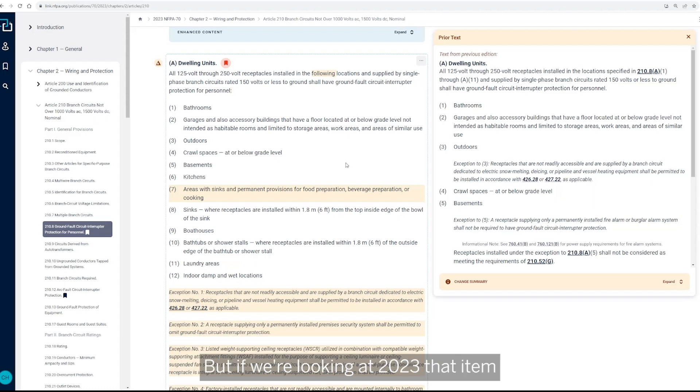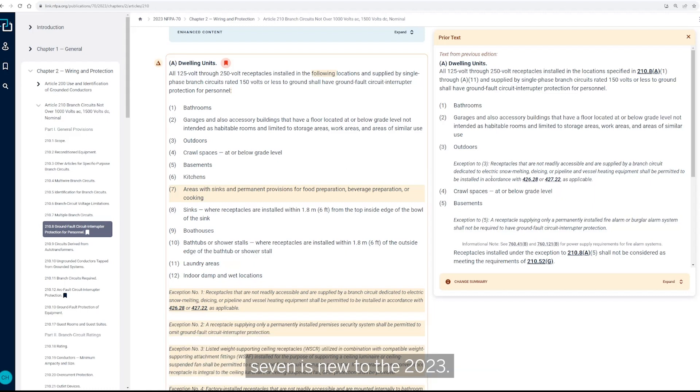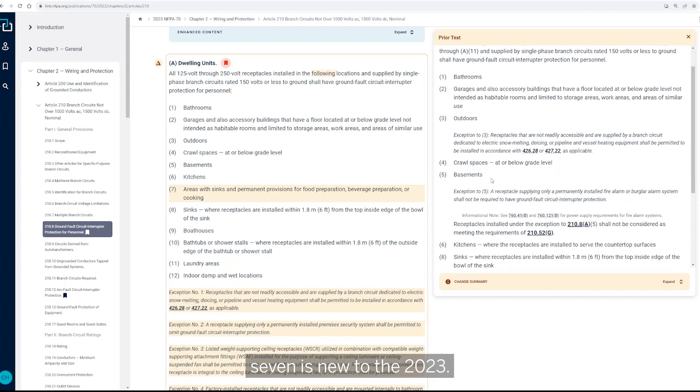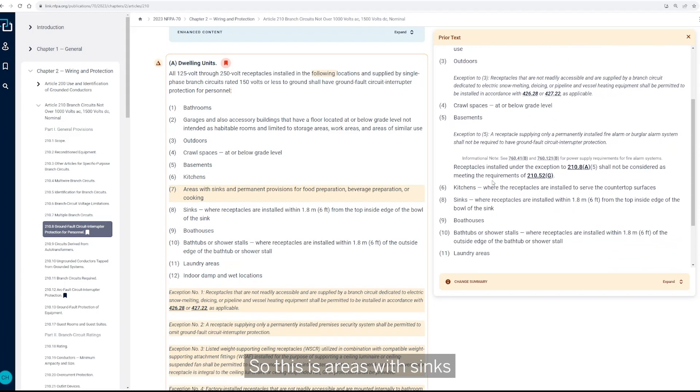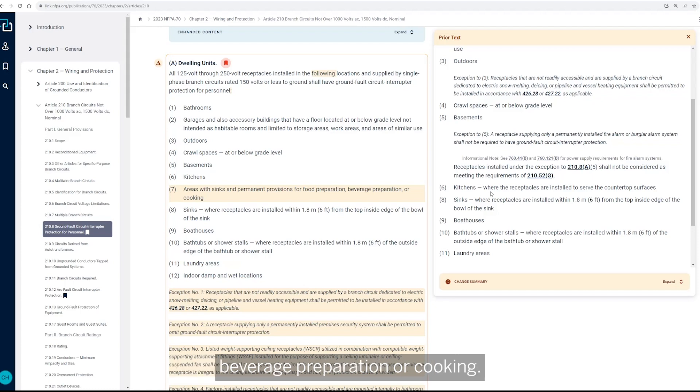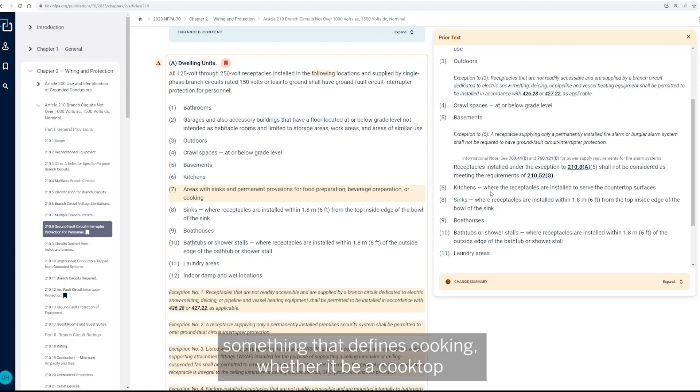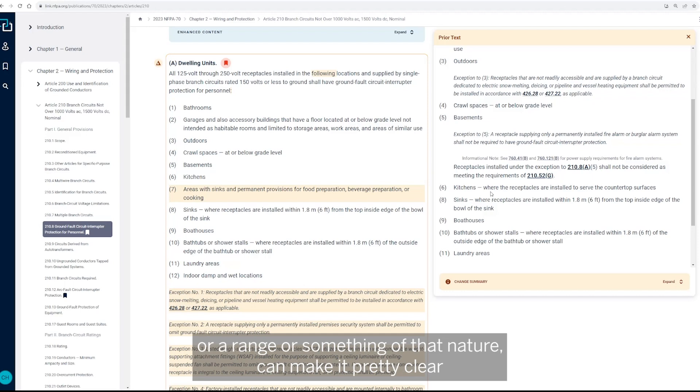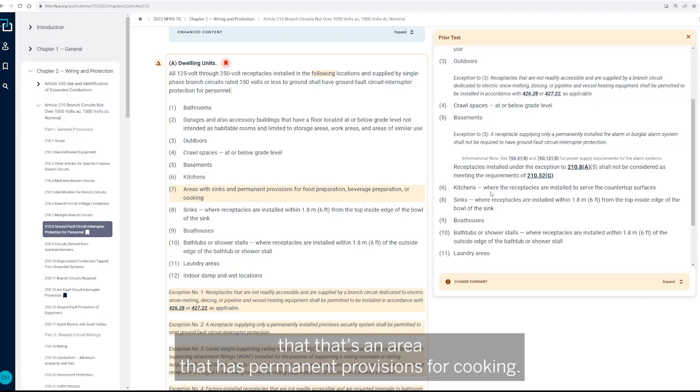But if we're looking in 2023, that item seven is new to the 2023. So this is areas with sinks that and permanent provisions for food preparation, beverage preparation, or cooking. So I think in those areas, something that defines cooking, whether it be a cooktop or a range or something of that nature, can make it pretty clear that that's an area that has permanent provisions for cooking.